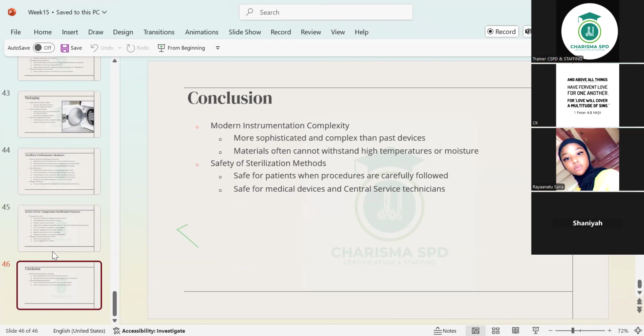And that will tell you why most hospitals don't have the ETO or the ozone. Everybody thinks of rapidity in this kind of process. So with low temperature sterilization, the hydrogen peroxide becomes more in demand than the other ones because it gives you a rapid cycle. The end result or the byproducts are not harmful, they're not toxic. But then it's my opinion though. You have your own opinion about time and toxicity. But if I'm evaluating the 3, I think that will be my best choice. But depending on the hospital, the facility, the rapidity of the turnover of instruments and all that. So that is up to the directorate to take care of.